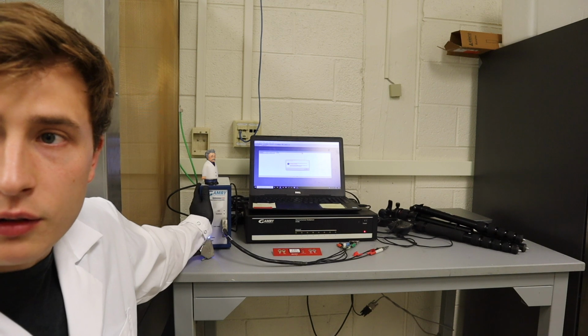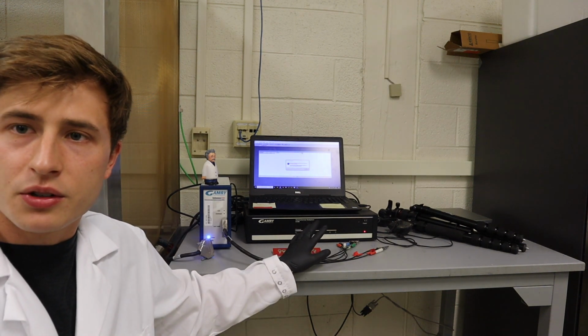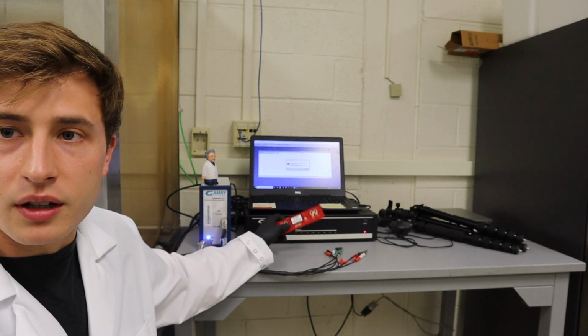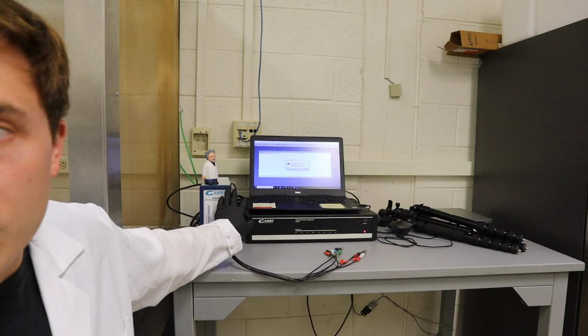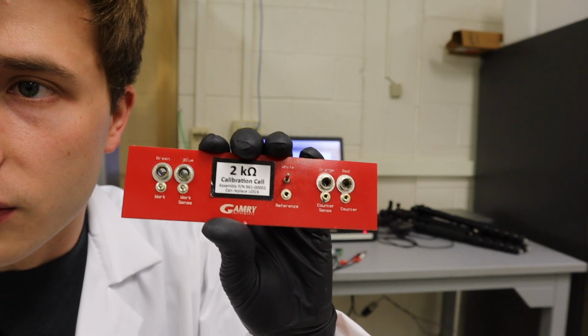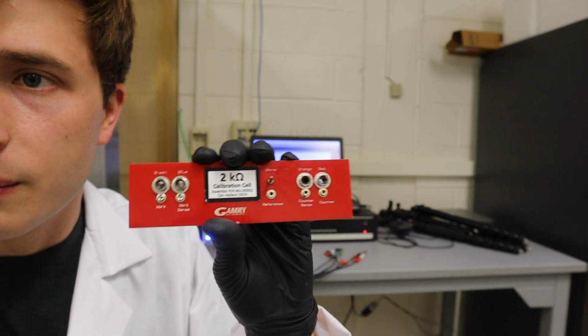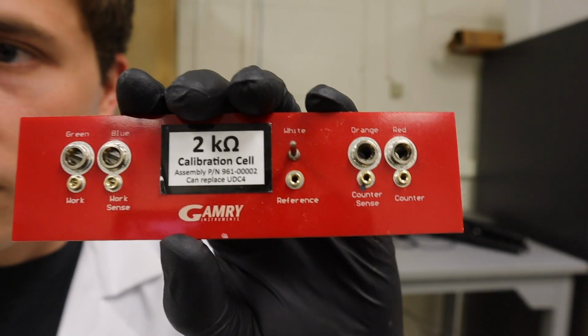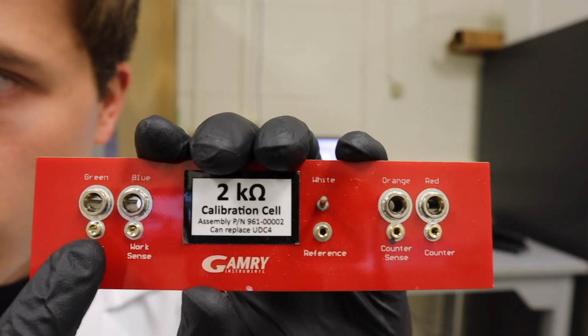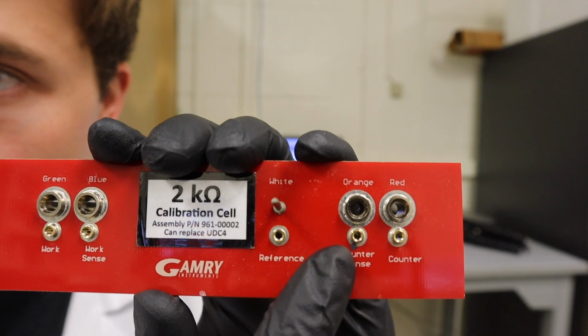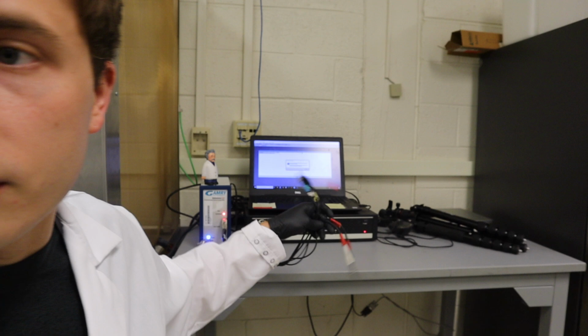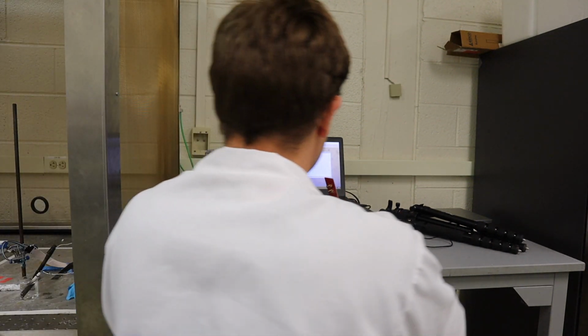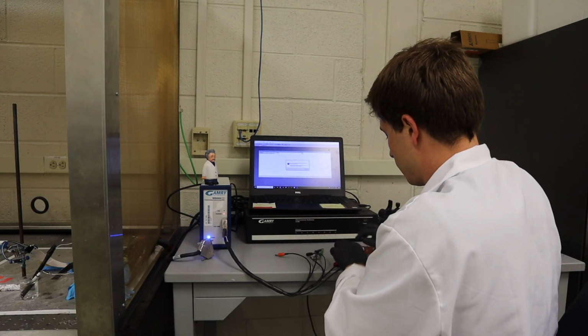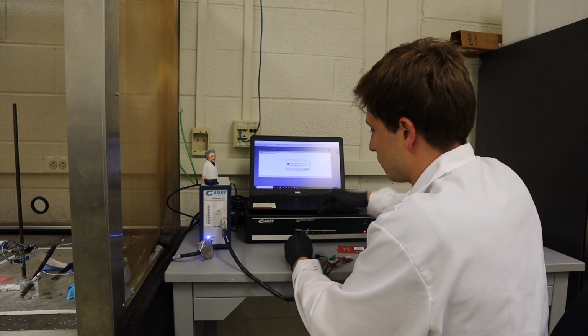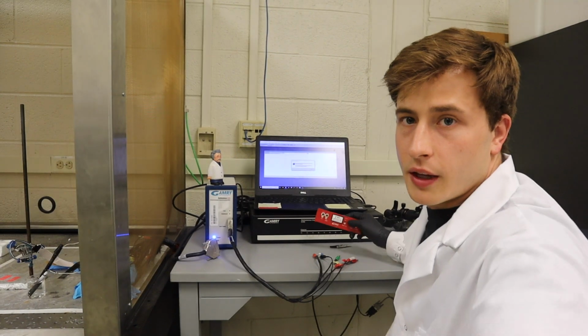What you need for all of this is really just the Gamry itself. You don't need the multiplexer. I can cover how to do the multiplexer in a different video, but for now we'll just talk about how to calibrate the Gamry itself. To do that, all you need is the Gamry, your computer, and this calibration cell. It should come with the Gamry. It's a 2 kilo ohm calibration cell. On this calibration cell, there's a socket for the green, the blue, the white, the orange, and the red pins, all of which are on the Gamry system itself right here. All you need to do is connect the pins onto this red dummy board, and you can do all of that here.